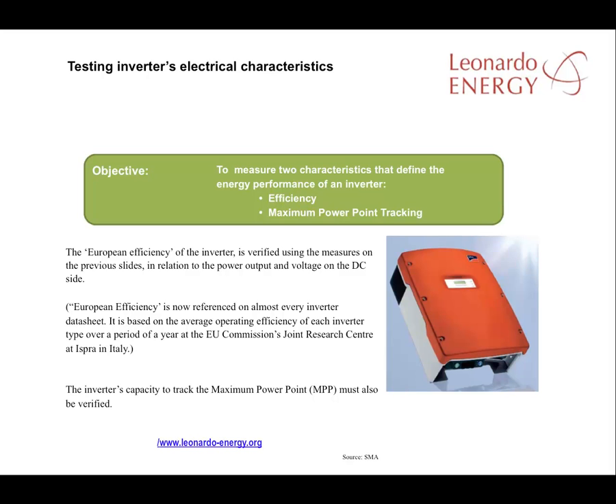The most important characteristics of an inverter are its efficiency and its maximum power point tracking. There are two measures of the efficiency of an inverter: the efficiency defined by the inverter manufacturer, and also the inverter's European efficiency, which is dependent on the inverter's load on the DC side. It's very important to verify that the inverter is working at its maximum power point, as this sets the maximum production from the modules in the PV facility.